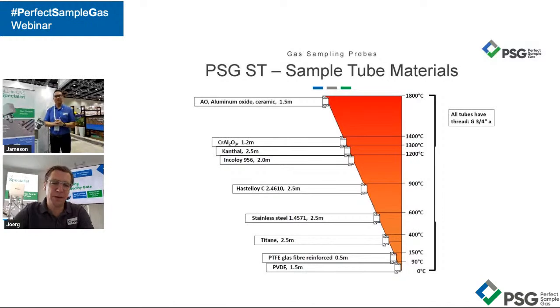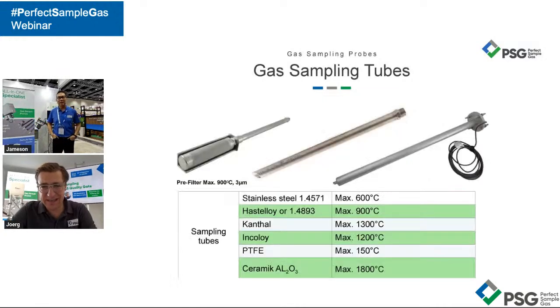That is a very good point, James, and I thank you for stressing this. What James just says is that if you have any condensation already happening in your gas sampling tube, you can have the best probe afterwards, or the best heated sample line, the best conditioning system, but the results will not be reliable and will not be accurate. And I think this is something very special.